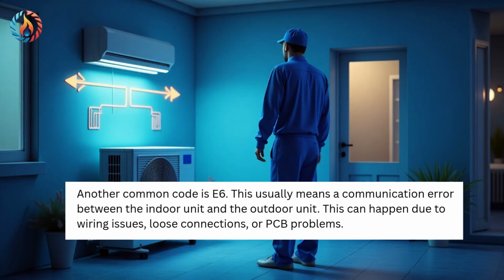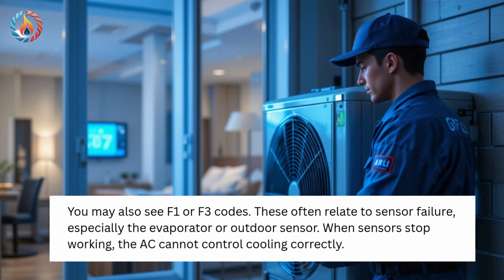Another common code is E6. This usually means a communication error between the indoor unit and the outdoor unit. This can happen due to wiring issues, loose connections, or PCB problems. You may also see F1 or F3 codes. These often relate to sensor failure, especially the evaporator or outdoor sensor. When sensors stop working, the AC cannot control cooling correctly.